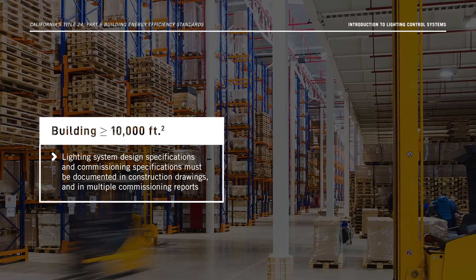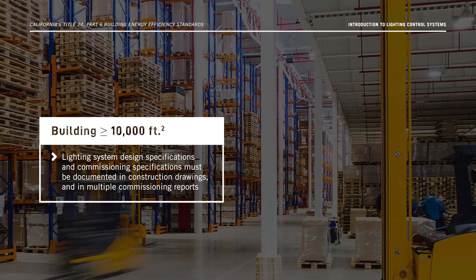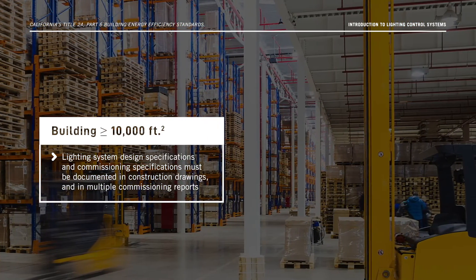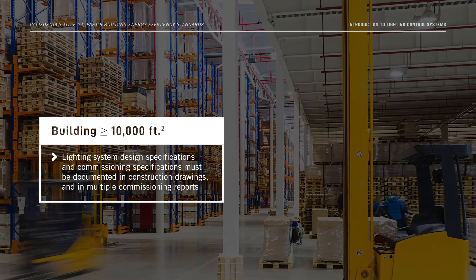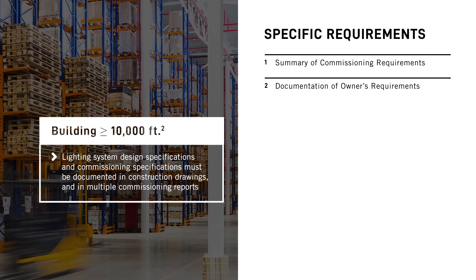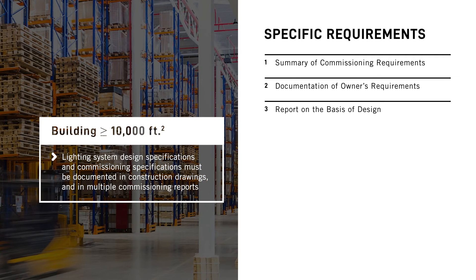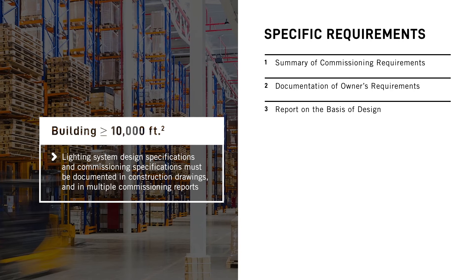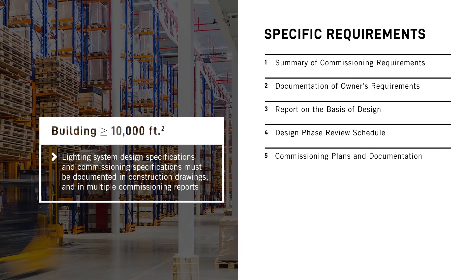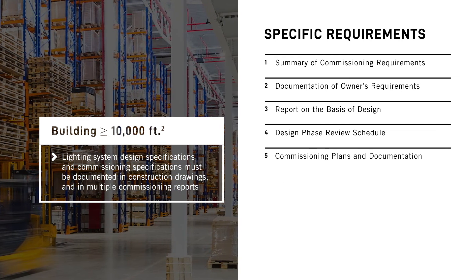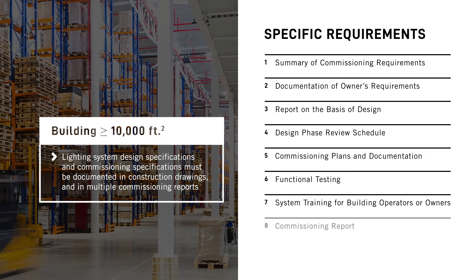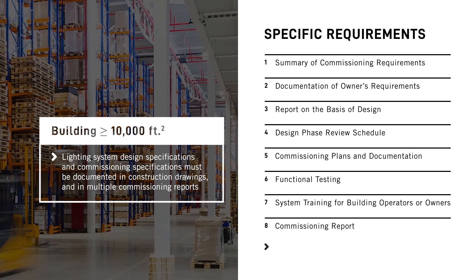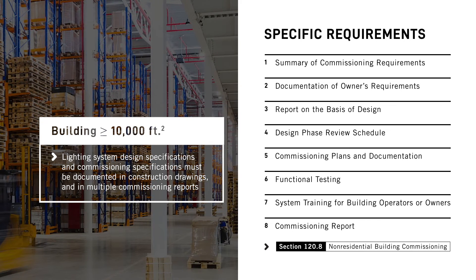The lighting system design specifications and commissioning specifications must be documented in construction drawings and in multiple commissioning reports. Specifically, you'll have to include documentation of owners' requirements, a report on the basis of design, a design phase review schedule, commissioning plans and documentation, functional testing, system training for building operators or owners, and the commissioning report. More information on all of these can be found in Section 120.8 of the Energy Code.